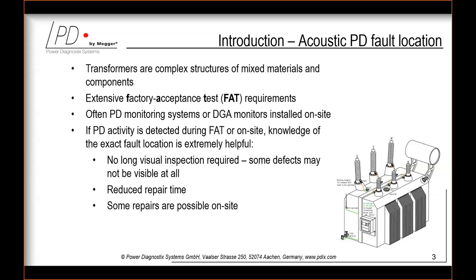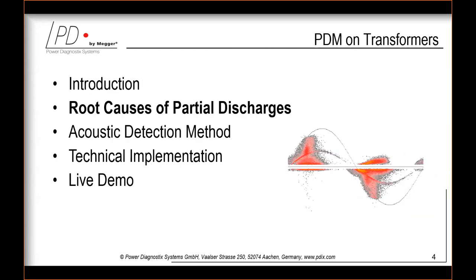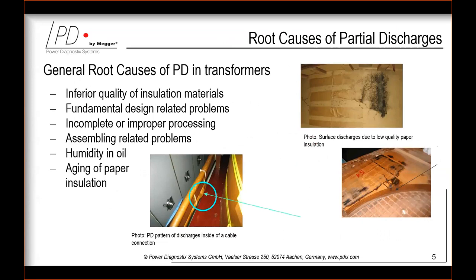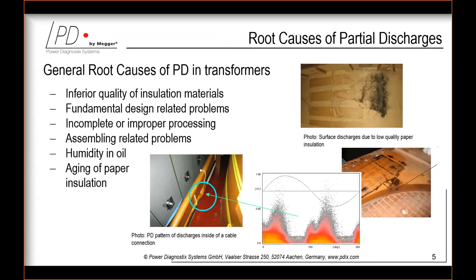Knowing the fault location reduces the need for lengthy visual inspection, since some defects may not be visible at all. This can reduce repair time, and sometimes repairs are even possible on site. The root causes of partial discharges in transformers are usually related to inferior quality of insulation materials, fundamental design problems, incomplete or improper processing, assembly problems, humidity in oil, or aging of the paper insulation.